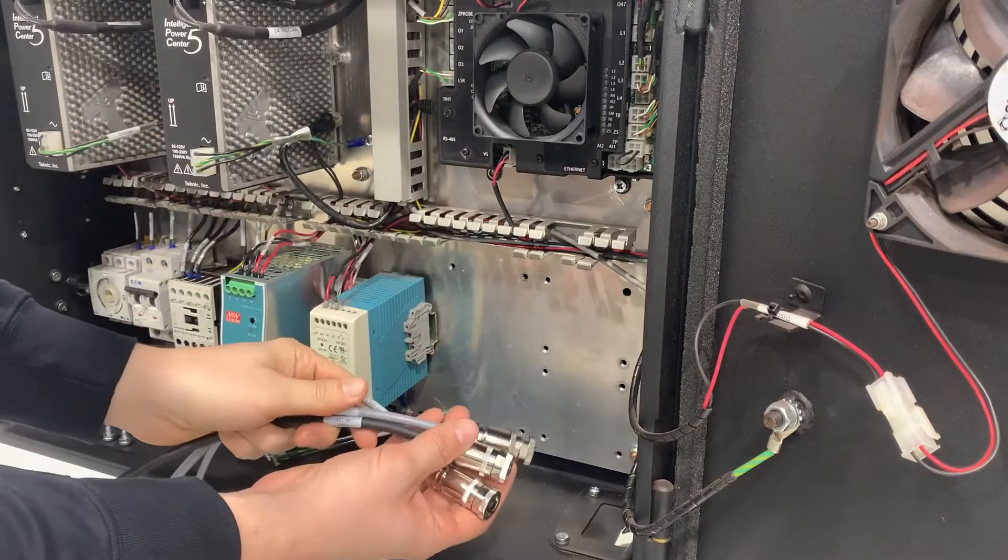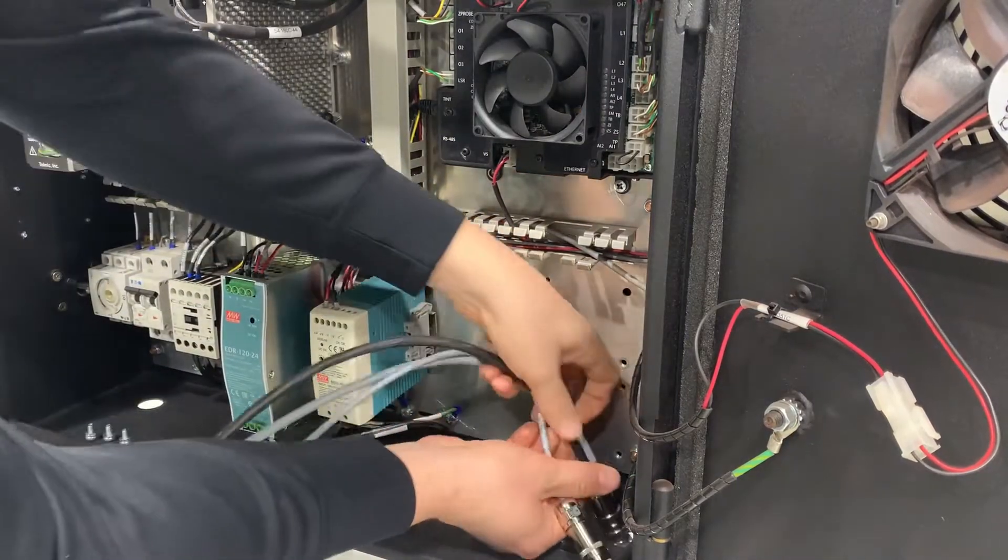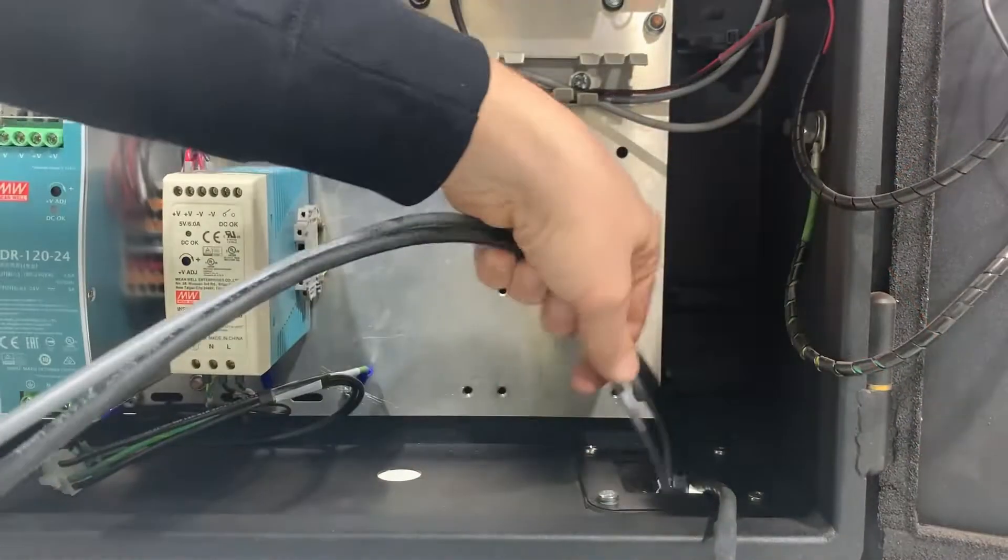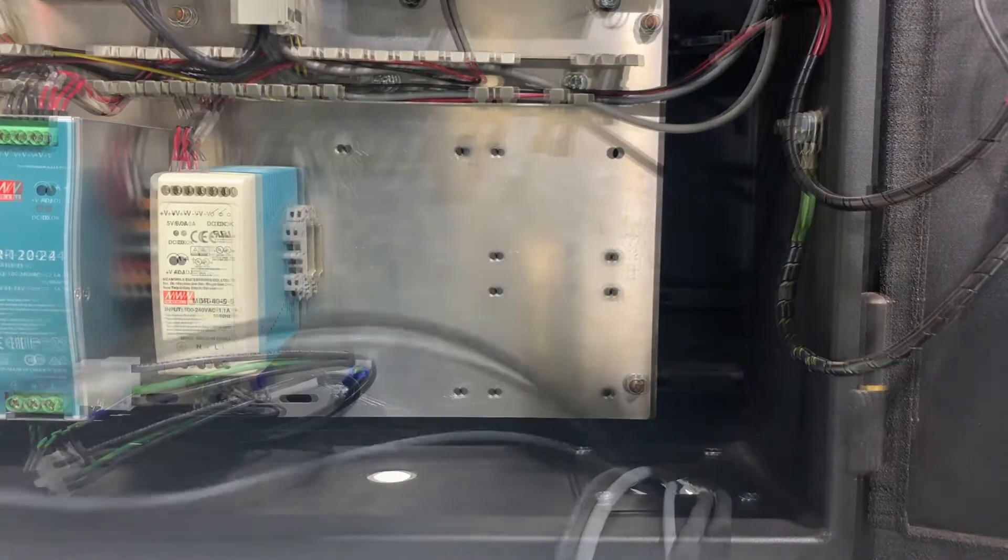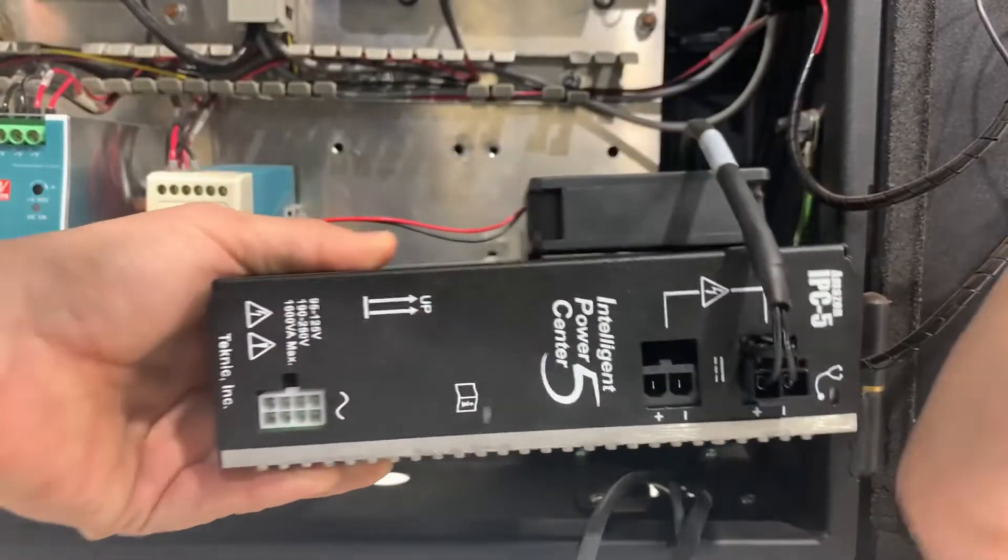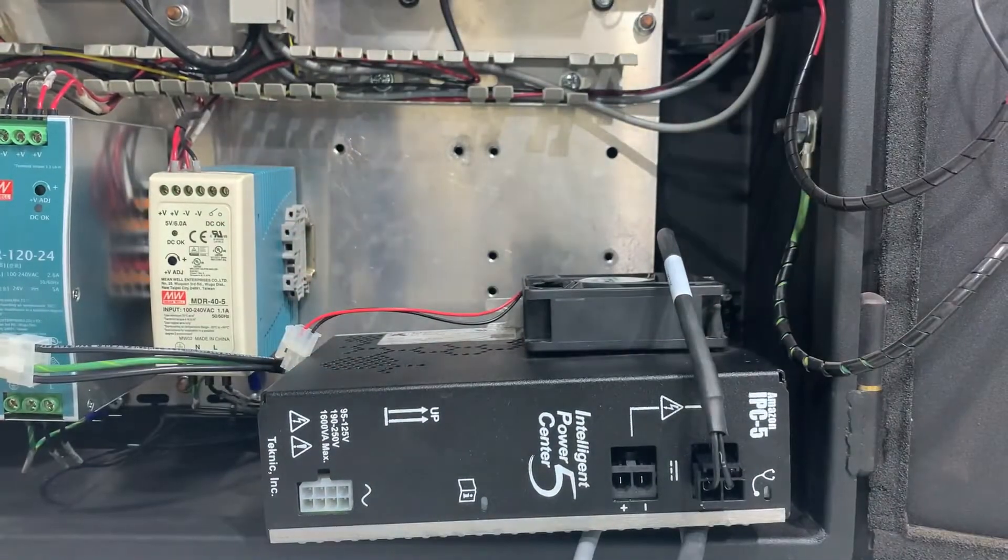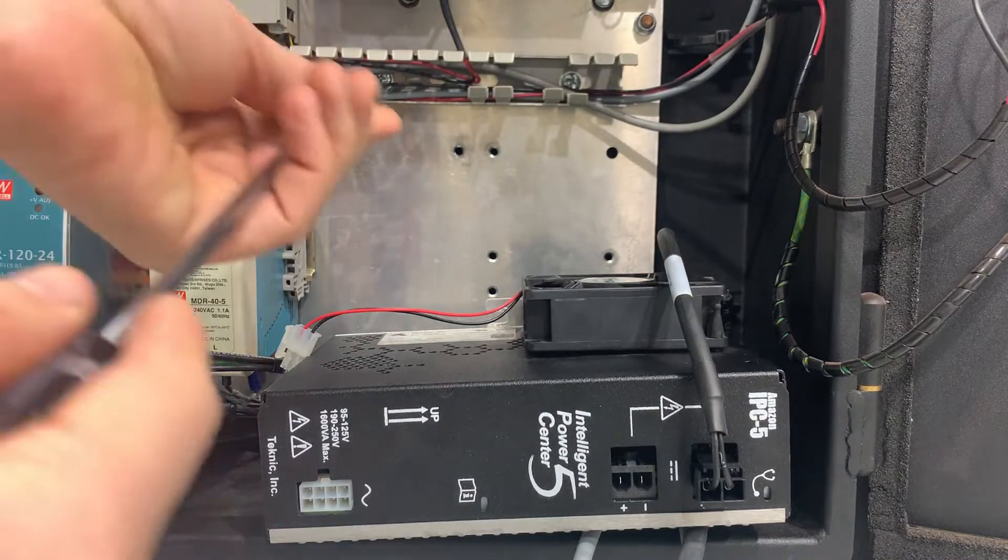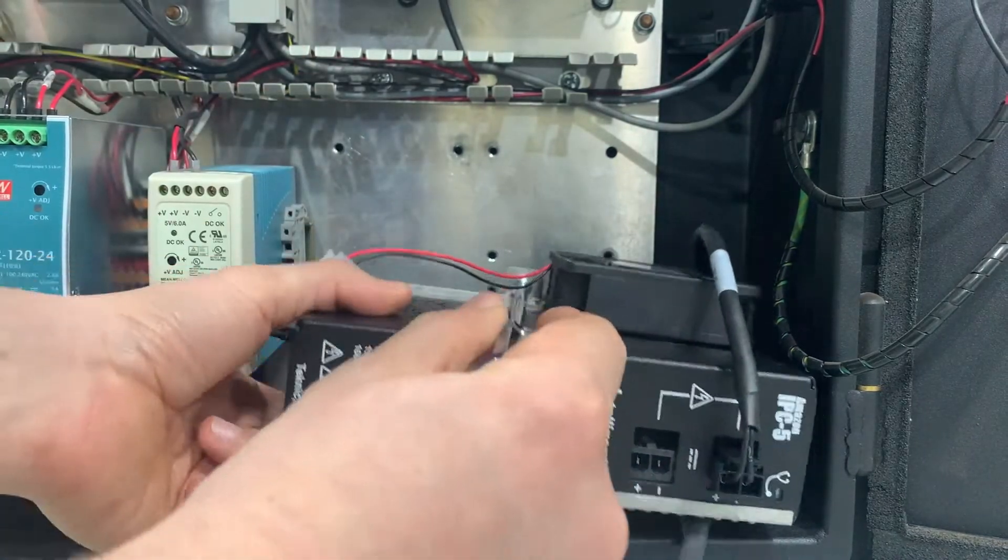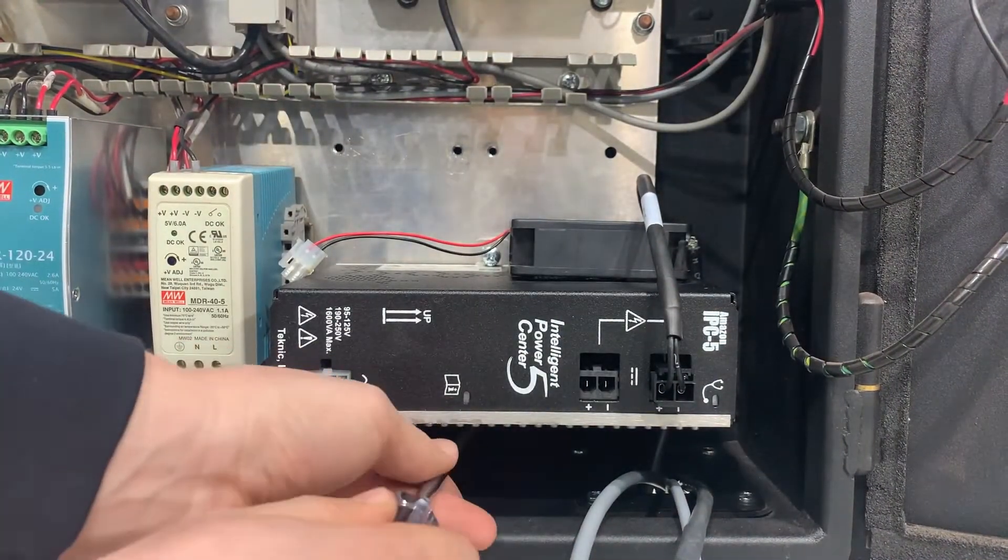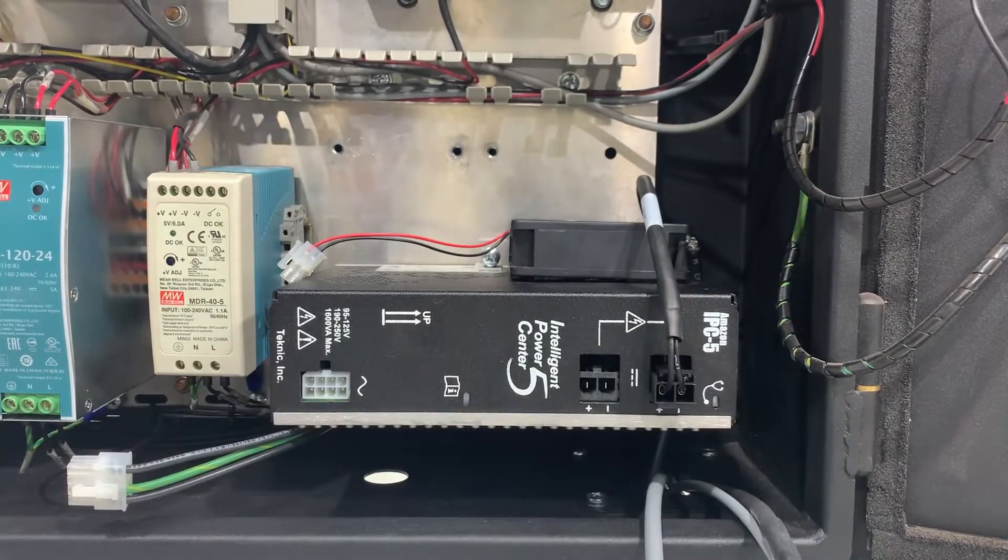Next, take the three cables that were supplied in the kit and feed their large shielded connectors through the bottom cable exit in the control panel. Feed the cables until there is enough slack remaining in the gray cables to reach the top of the control panel. Feed the black cable until you need to pick up the power supply with your second hand and then continue feeding until you can rest the power supply on the bottom of the box. Attach the power supply to the back plane using three M5 pan head bolts, lock washers, and flat washers. It is helpful to have a longer reach screwdriver for this step.